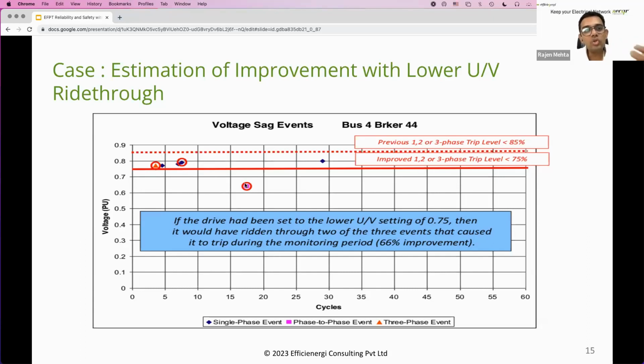The simplest solution which we could apply, and which worked beautifully to prevent almost 60% of the voltage sags from causing downtime to their medium voltage drive, was to change the under voltage setting of the drive. The under voltage setting was previously kept at about 85%. As you see over here, this dotted line shows the under voltage setting of 85%. Just reducing it to 75% caused almost 60% of the voltage sags to stop having an impact on plant downtime or that particular drive malfunctioning.